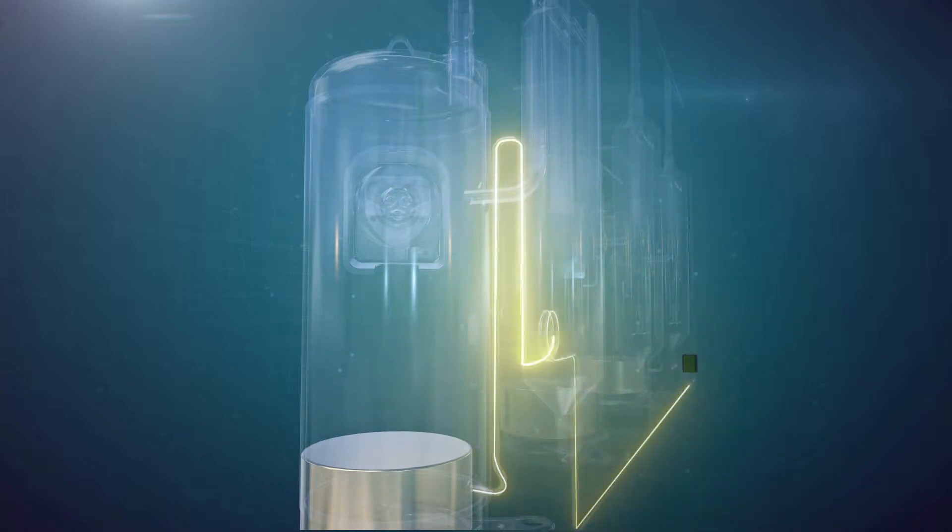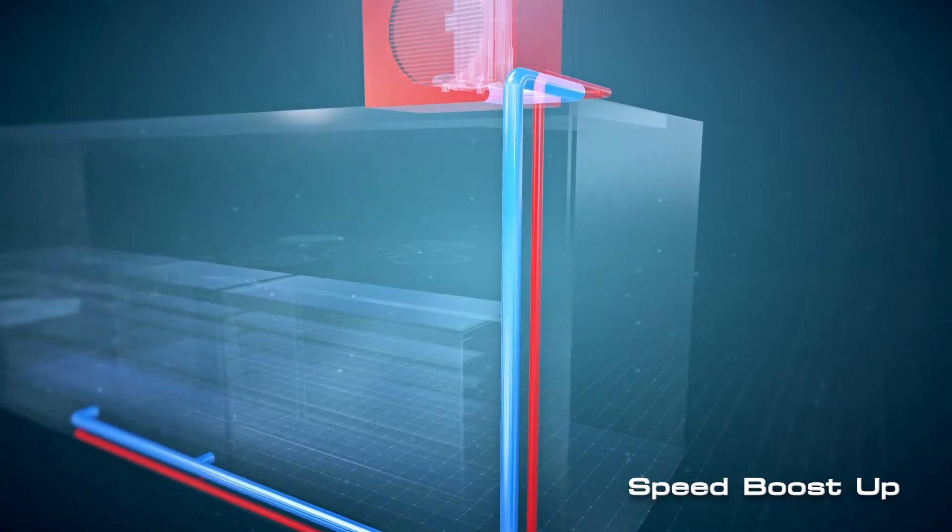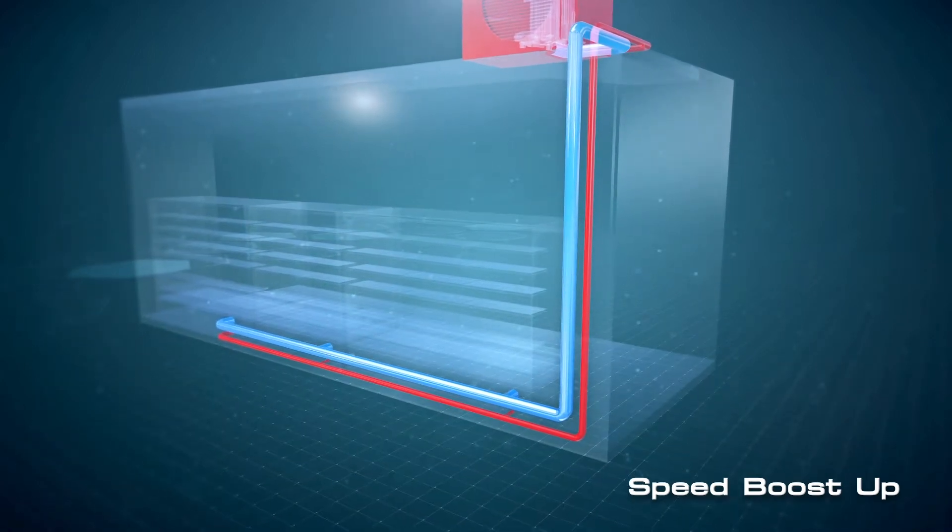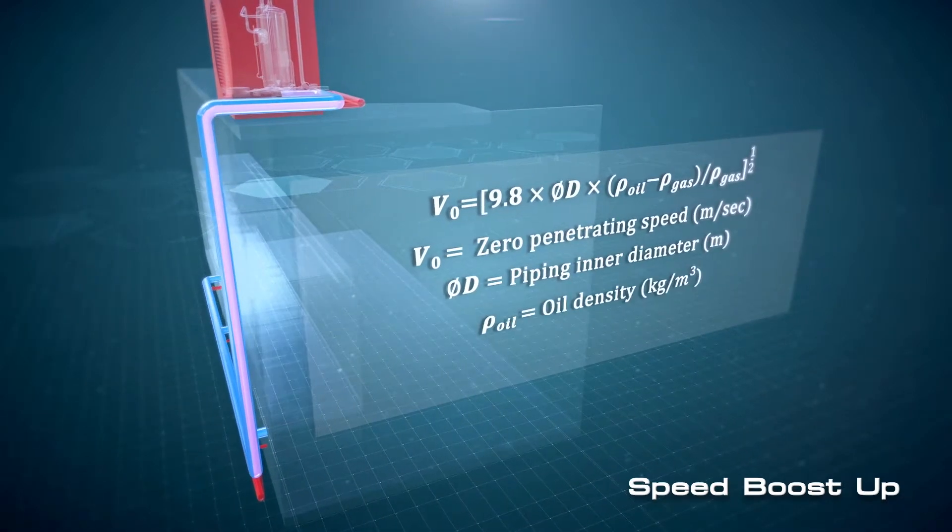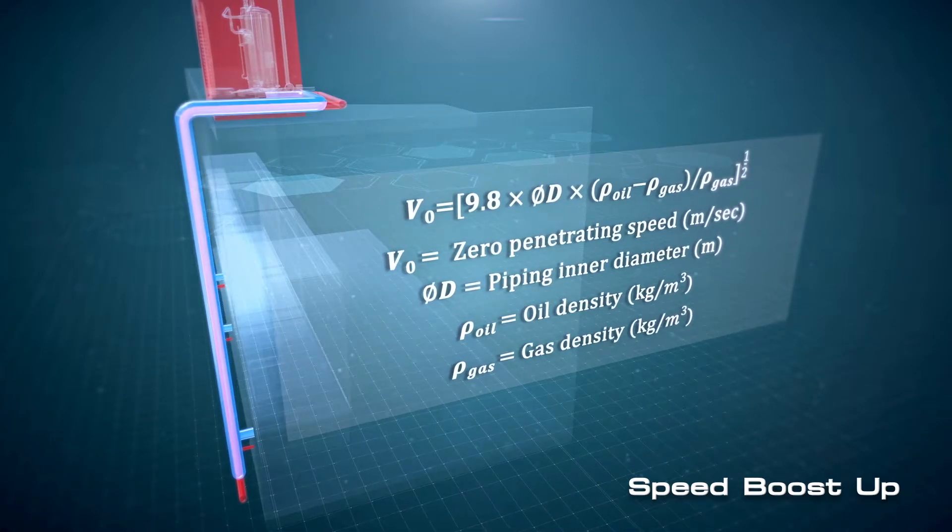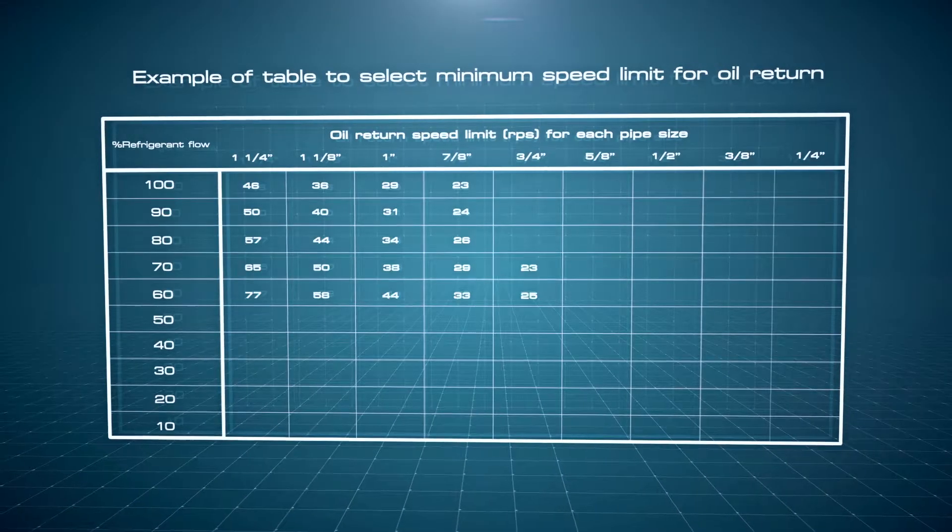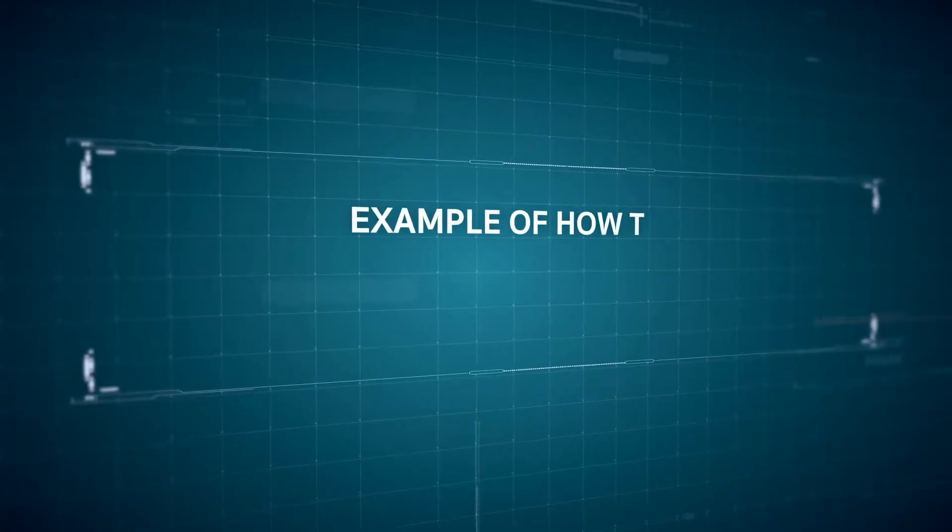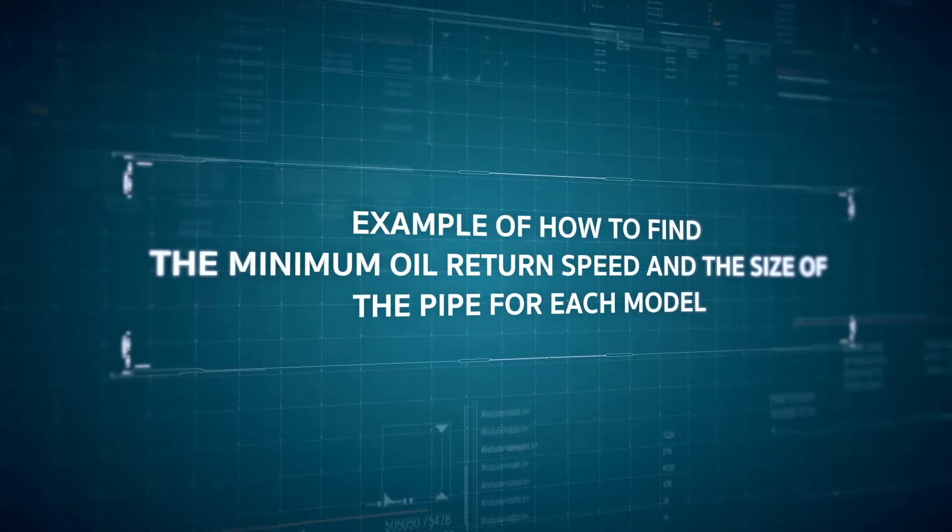The speed boost up technique is utilized in vertical piping, where the compressors are above the evaporators. The minimum oil return speed depends on the size of the pipe. That is, larger pipes require higher minimum oil return speed. The equation for calculating the minimum oil return speed, given the size of the pipe, is as shown. According to the equation, here is the list of minimum oil return speed of each compressor model, and here is an example of how to find the minimum oil return speed and the size of the pipe for each model.